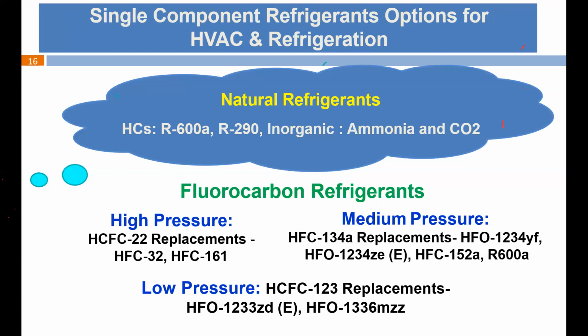And for the medium pressure refrigerant, which is R134A, the replacement is HFO refrigerant, HFO 1234YF and HFO 1234ZE. These refrigerants are all in the tetrafluoropropene category, but they have different trade names as far as the manufacturer is concerned. HFO means hydrofluoroolefin. So I'll tell you something about what HFO is.